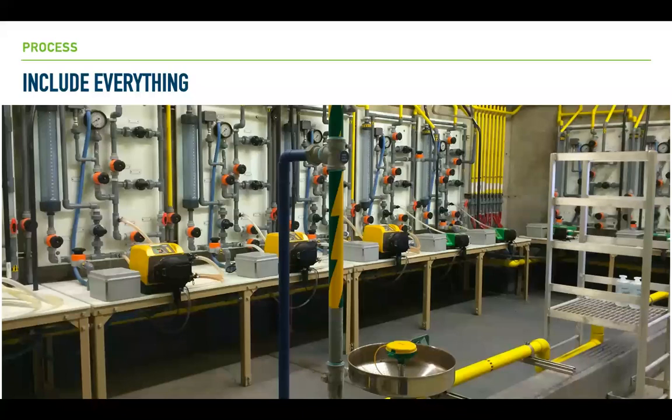All right, so one of the principles that we've got, and this is why we look at the system approach, is that we say include everything in the analysis. If you leave assets out, if you leave systems out, you will have undiscovered risk. And so this is an actual example, again, of one of the facilities that we worked with. What was on the books in the asset register were those yellow pumps. And there are actually 4 green pumps. They're a little bit off to the right side, and you can't really see it because of the ladder going over the berm. And so really, they only had 7 assets in the register related to this particular function in this facility.